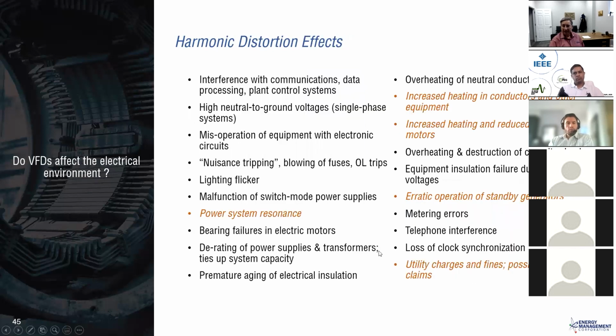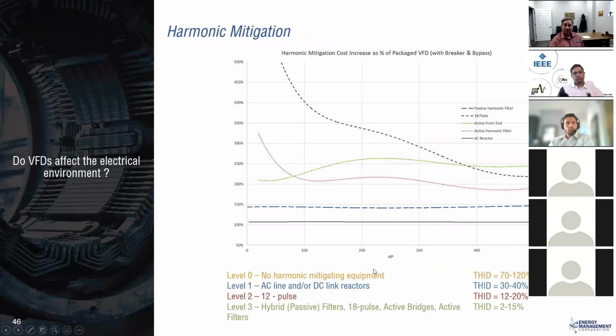Harmonic effects, I'm not going to spend time on that. I think you already are aware of some of the problems that can happen when the harmonics get too large. Clear back in '88, the mid '80s, when we got a patent on this, harmonics were thought by most vendors to not be important. We had one individual at a university, Utah State University up in Logan, an engineer that was very ahead of his time. He said, I don't want another drive coming into my facility that doesn't have some harmonic correction. And that was clear back in those early days.